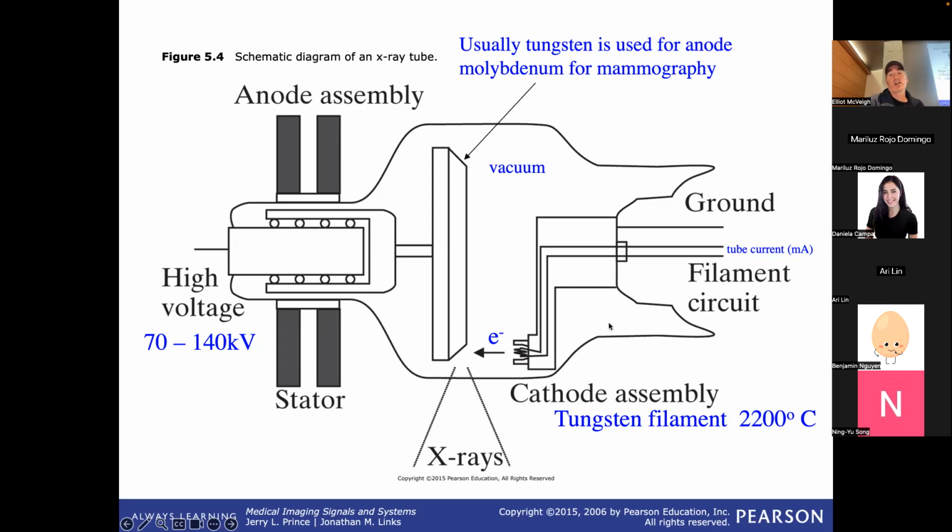Okay, these are a big deal in this field, and in CT, you need electron or X-ray sources that produce very high fluence of X-rays, because we want to image very quickly. So if we make a CT scanner where we're only radiating the patient for, say, 100 milliseconds, we need a lot of X-rays in that 100 milliseconds.